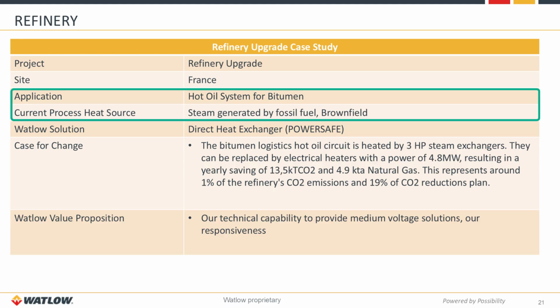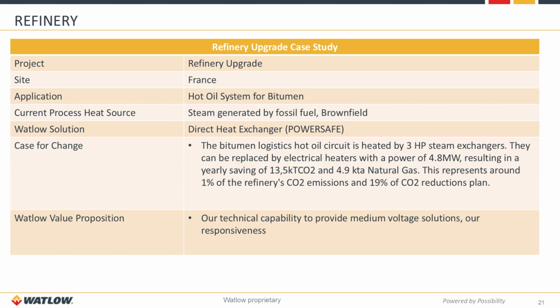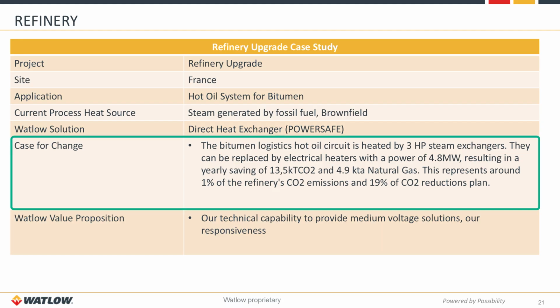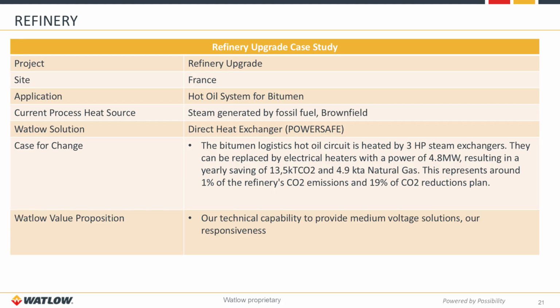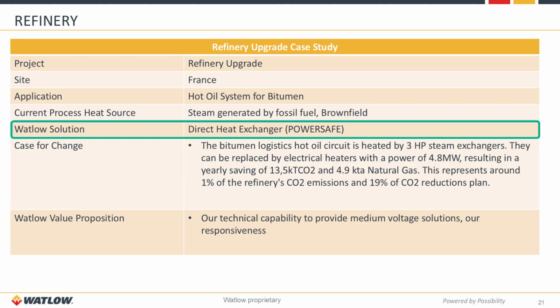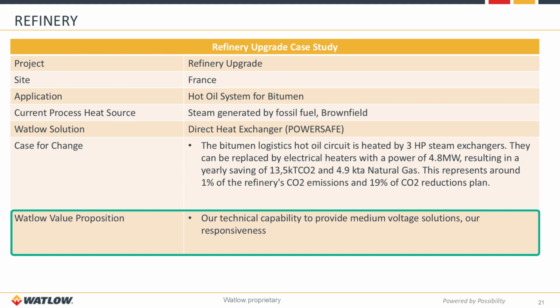This was a hot oil system. Again, they were using a steam-generated type of heat exchanger powered by fossil fuel. In this particular case, again, the case for change was based on reducing those overall emissions of CO2 and the usage of natural gas within the system. That particular usage of natural gas represented around 1% of the refinery's CO2 emissions and about 19% of their CO2 reduction plans moving forward. Again, we were able to replace that with a medium voltage electric heater and provide our technical capability along with the medium voltage solution to ensure that they were meeting their objectives.